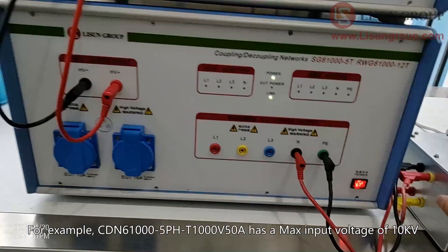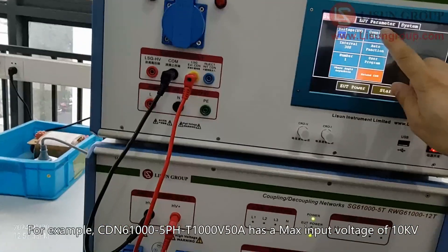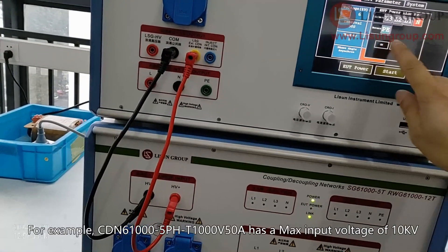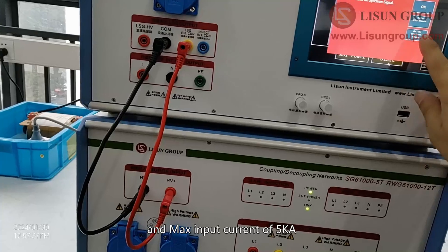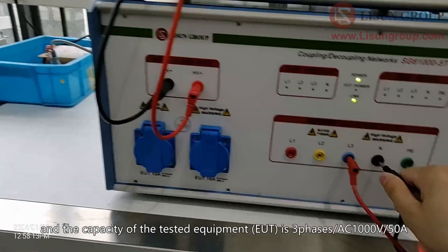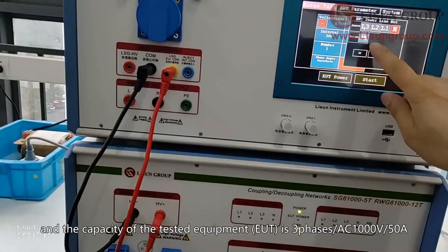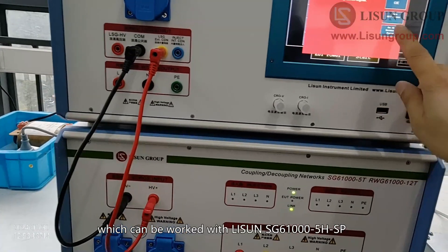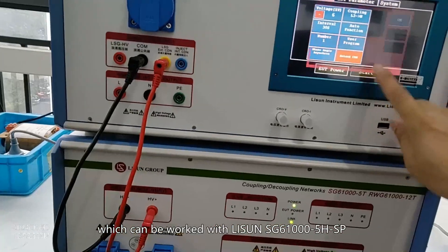For example, the CDN61000-5PH-T1000V50A has a max input voltage of 10 kV and max input current of 5 kA. The capacity of the tested equipment, EUT, is three-phase AC 1000V / 50A, which can be used with LISUN SG61000-5H-SP.